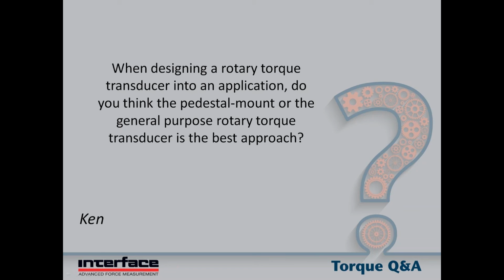In some cases, say a fixture, where I'm going to break it down and reinstall a test article over and over again, the floating mount can be a pain because every time you break that test connection, the sensor is allowed to flop or sag, and you don't have any support. So it might be in that case a pedestal or a foot mount is preferred, but usually we start talking about floating installations and then move to a foot mount if that ends up making more sense.